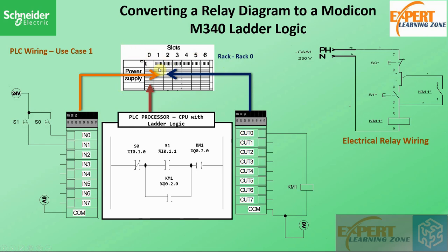Our PLC processor is located on slot 0 in the rack — this is rack 0. The processor is always located on slot 0, and beside it is the power supply. Our input module is in slot 1 and our output module is in slot 2. These are different address locations or references that we use to access different pins on the input and output modules.